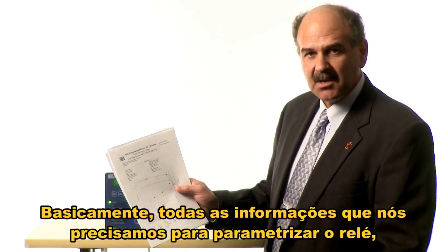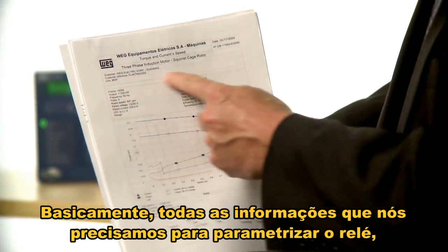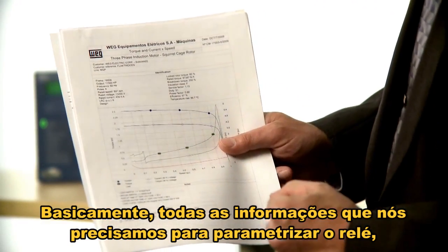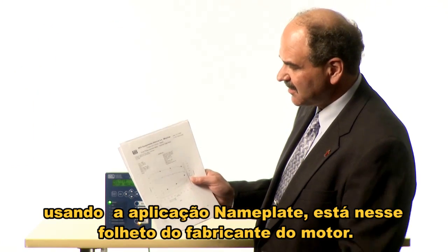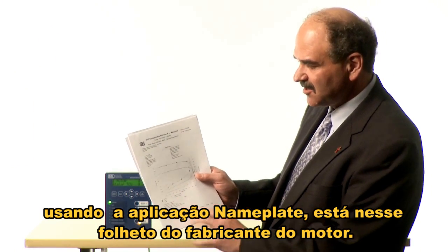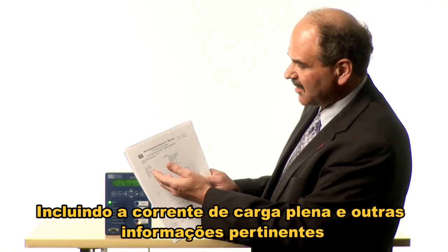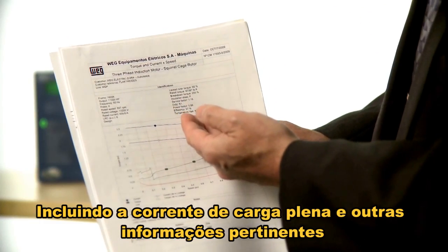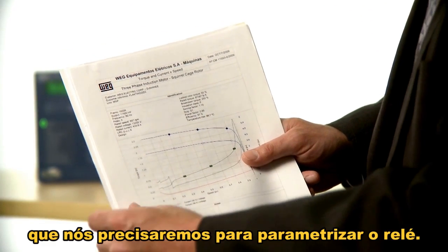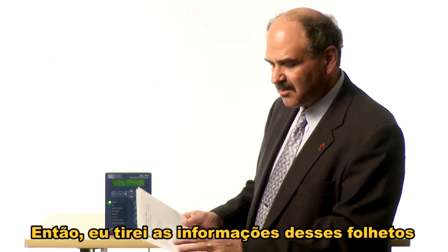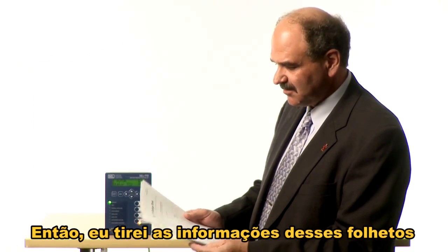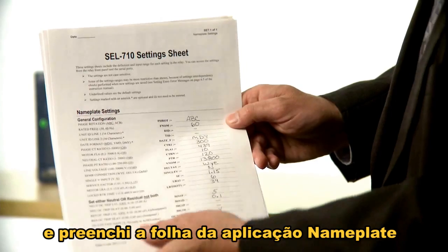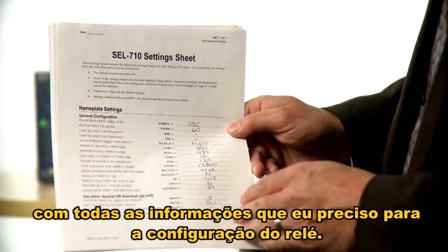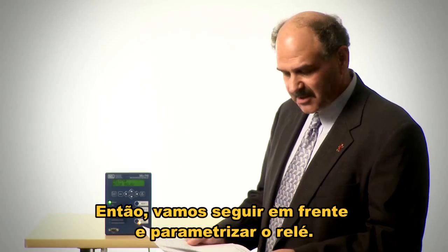So after pulling that information off of the one-line diagrams, I went through and pulled out the motor data sheet. Basically, all the information we need to set the motor nameplate application in the relay is provided on this nameplate application data sheet right from the motor manufacturer, including the full load current and any of the other pertinent information we're going to need to set the relay. So I pulled all this information off those sheets, and I filled out my nameplate application settings sheet with all the information I need to set the relay. So let's go ahead and do that.